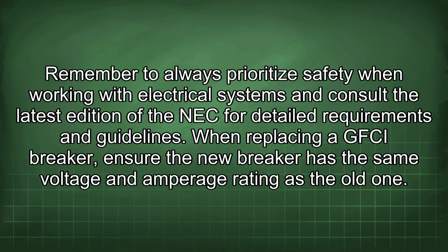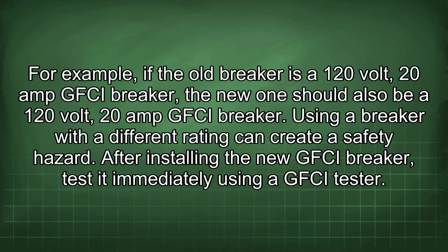requirements and guidelines. When replacing a GFCI breaker, ensure the new breaker has the same voltage and amperage rating as the old one. For example, if the old breaker is a 120 volt 20 amp GFCI breaker, the new one should also be a 120 volt 20 amp GFCI breaker. Using a breaker with a different rating can create a safety hazard.